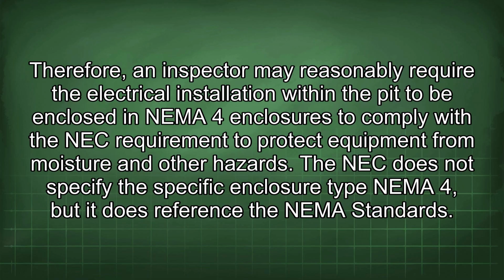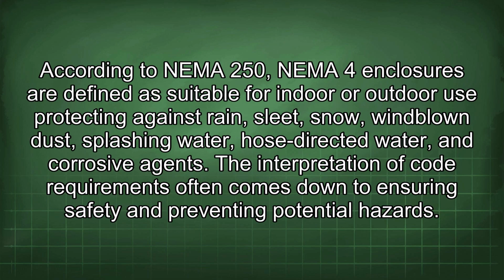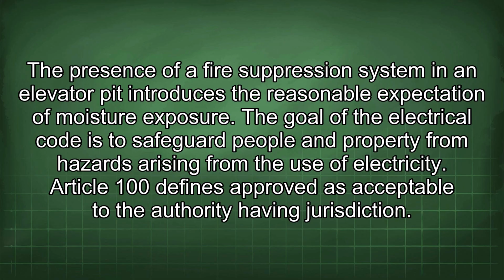The NEC does not specify the specific enclosure type NEMA 4, but it does reference the NEMA standards. According to NEMA 250, NEMA 4 enclosures are defined as suitable for indoor or outdoor use, protecting against rain, sleet, snow, wind-blown dust, splashing water, hose-directed water, and corrosive agents. The interpretation of code requirements often comes down to ensuring safety and preventing potential hazards. The presence of a fire suppression system in an elevator pit introduces the reasonable expectation of moisture exposure. The goal of the electrical code is to safeguard people and property from hazards arising from the use of electricity.